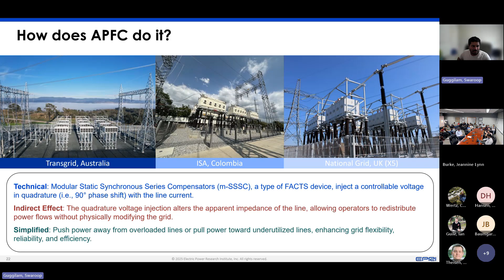In simplified terms, say you have two transmission lines. One has a rating limit of 50 megawatts, and the other has a capacity of 500, but the flow is 60 and 400. So this line is right now overloaded. If I switch off this line or take it out of service, the entire flow goes through the other line, and it's still within the limit.